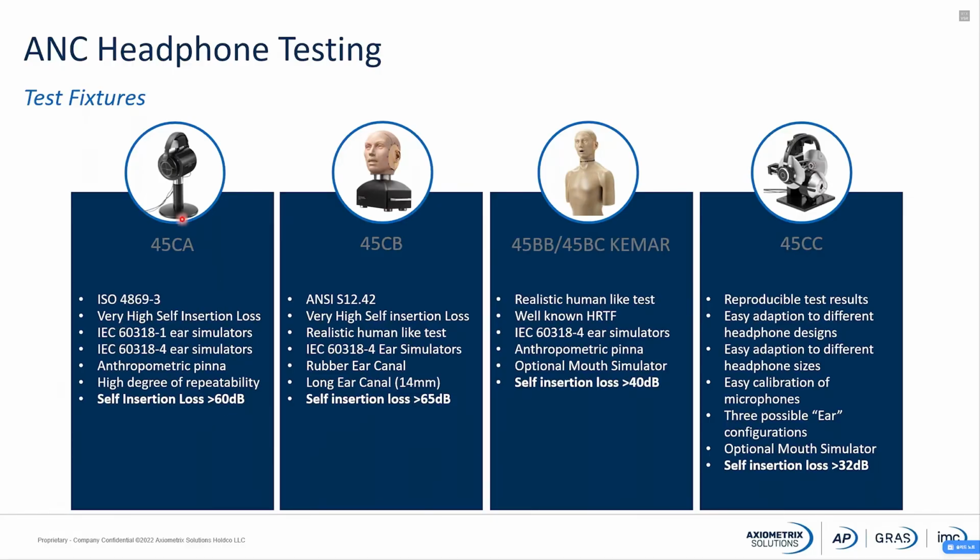You can equip this test fixture with many different types of ear simulators. You can use a realistic pinna, such as the anthropometric pinna. This is the most used configuration for ANC tests, and this is the one we are going to be using today.